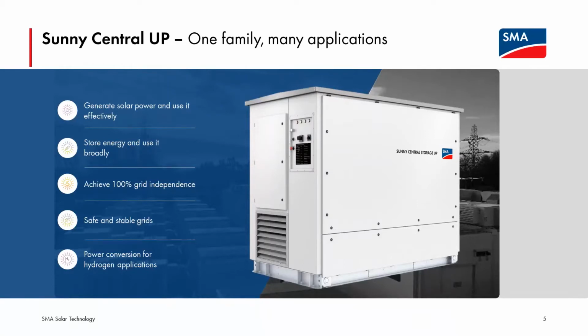Sunny Central Up is a family of inverters sharing the same hardware and software platform with minor variations. This makes it very convenient to realize different types of applications. Efficient conversion of solar power is done by the classical Sunny Central photovoltaic inverters. With a true DC input range of up to 1500 volt DC and a power rating of up to 4.6 megawatts, it's really a workhorse in solar power generation.